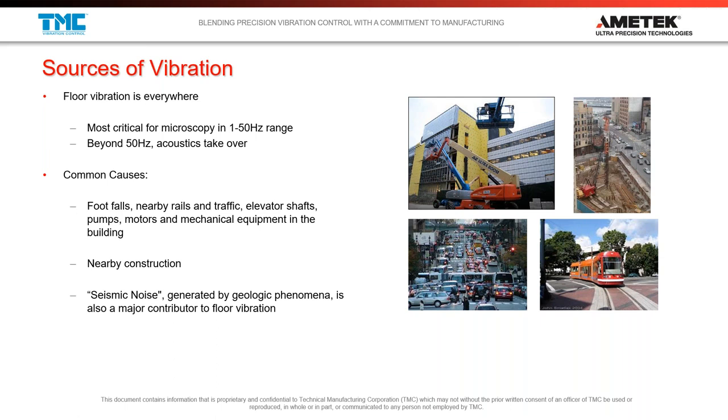But once you start getting past 50 hertz, you start getting into audible acoustics and moving air in the facility and things like that. There's really not a whole lot you can do about that from a floor vibration isolation perspective. That's where you start looking at facility remediation or acoustic enclosures and things like that. And floor vibration in particular is typically caused by things like footfalls, people walking in the building, people walking in the lab. If you have a large building and it's filled with people that are walking, the period of human walking is about half a second, which is roughly two hertz, a two hertz rate of impact. And that cumulative effect of everybody walking in the building tends to be a two hertz building resonance.